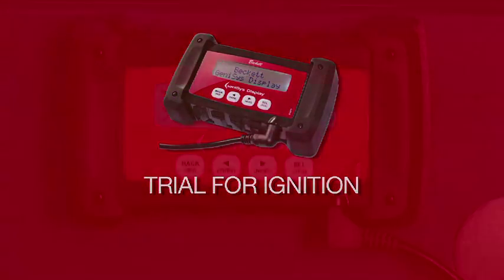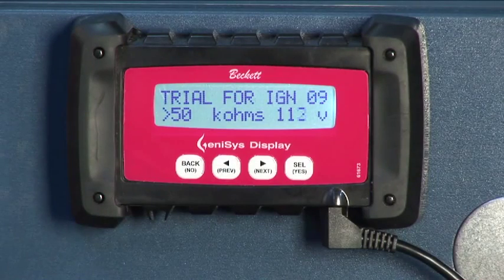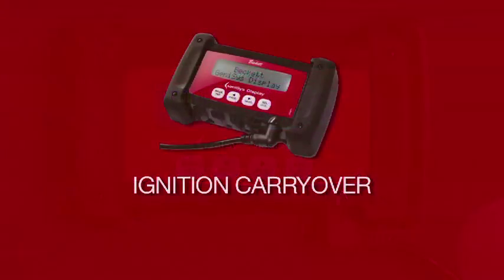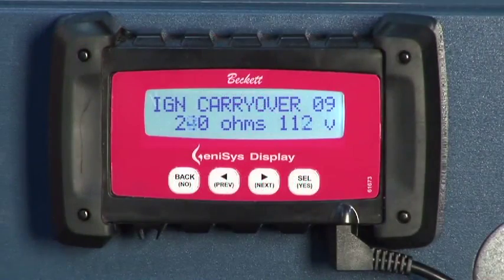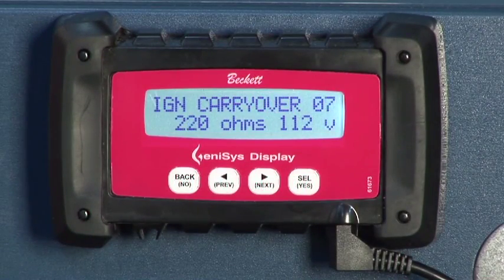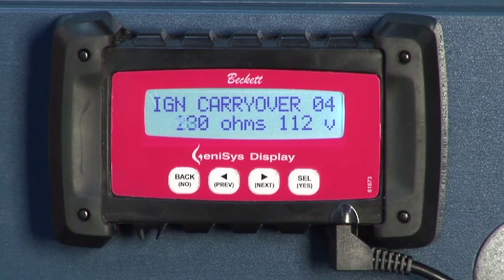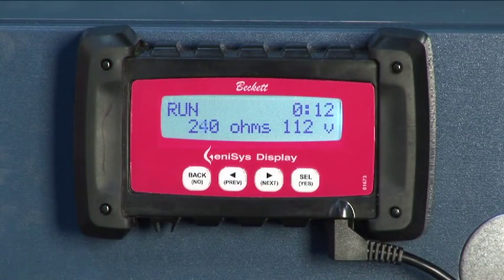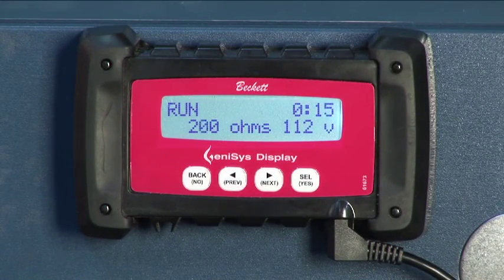Trial for IGN: This screen displays the amount of time left in trial for ignition before the control locks out. IGN carryover: This screen displays the amount of time that the igniter will remain on after the CAD cell detects a flame. Run: The burner run screen displays the number of minutes and seconds the burner has been firing.